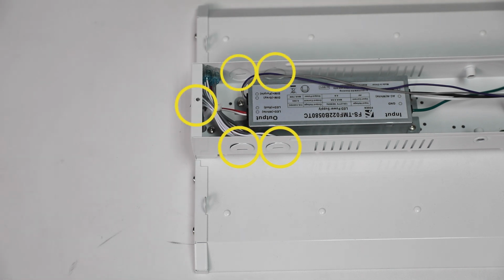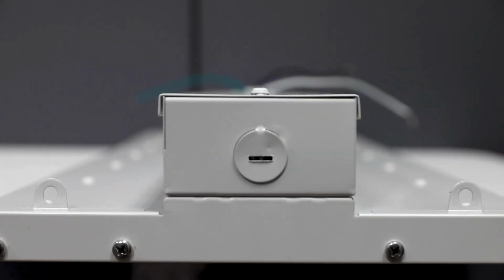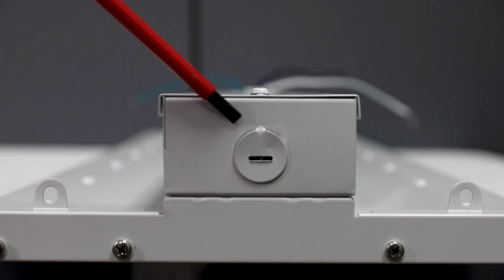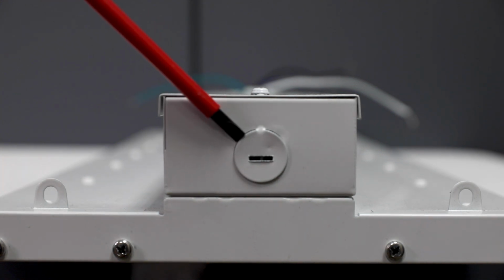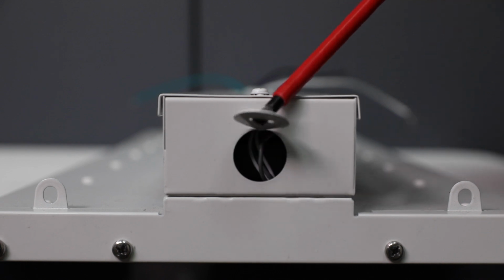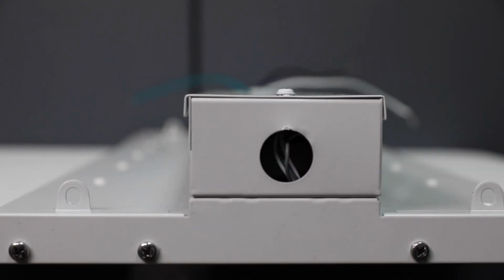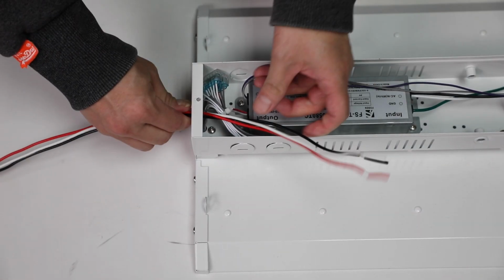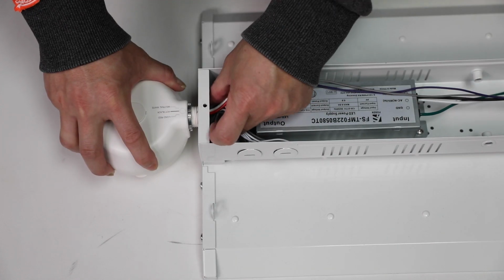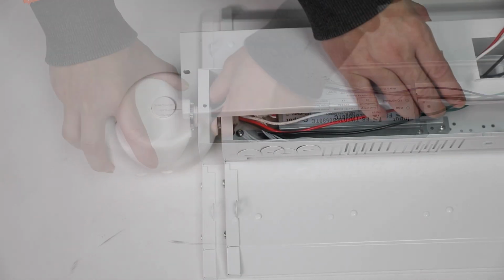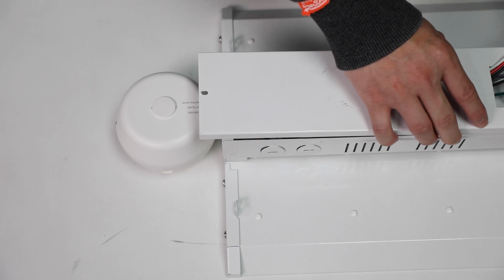Typically, you want an unobstructed view of the floor below, so the ideal location is on the bottom or side of the fixture. There should be knockouts on the high-bay light fixture. Remove the desired knockout from the light fixture. Pull the wires through the knockout and secure the sensor to the light fixture with the connector nut. Place the cover back on and thread the wires through the access port.